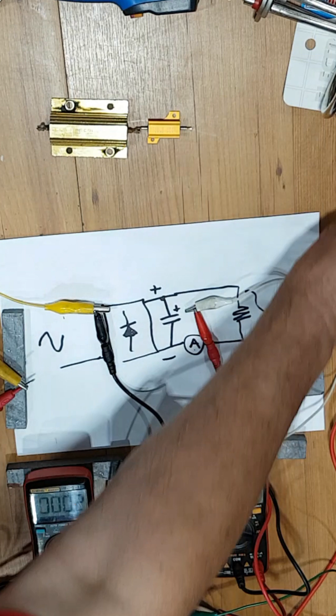This 100 ohm we tested at 50 volts, which is the maximum for this capacitor, so we cannot connect more than that. Let's do the same thing, 50 volts. I want to see 480 or so milliamps here, if I remember the previous test. We're on 50 volts there, and 460, awesome. 47, 48, 49, 50, 480, 490 milliamps. That's half an amp, 0.49 amps. So I'm happy this is reacting the same now as it did on the AC test.